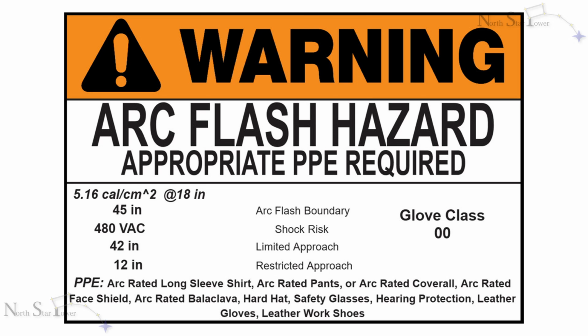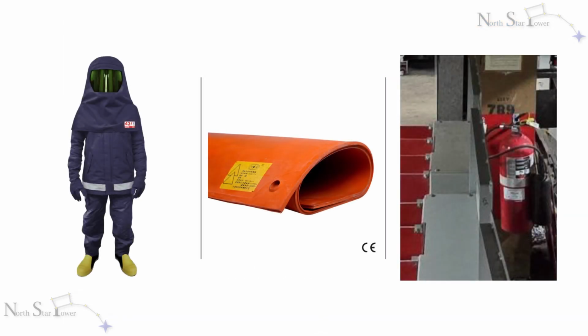Some substations are located within the vicinity of working personnel, and it is paramount to ensure that employees understand the hazards involved with working nearby. Also, check the room for fire extinguishers, arc flash gear, and insulated blankets. How about what the room itself is made of? If an arc flash occurred, would the rest of the building be safe?